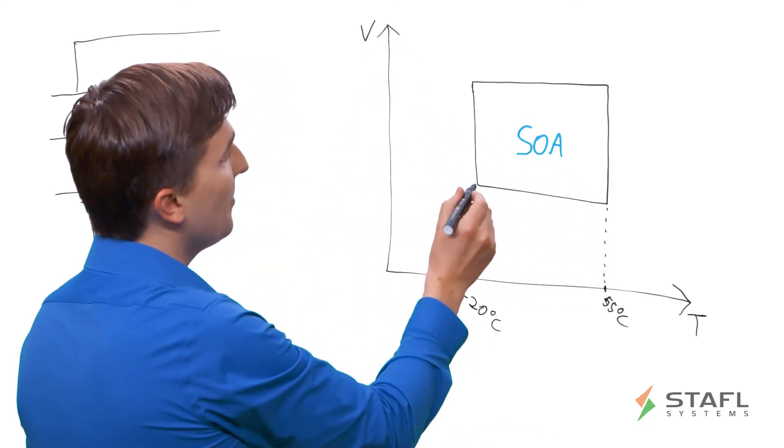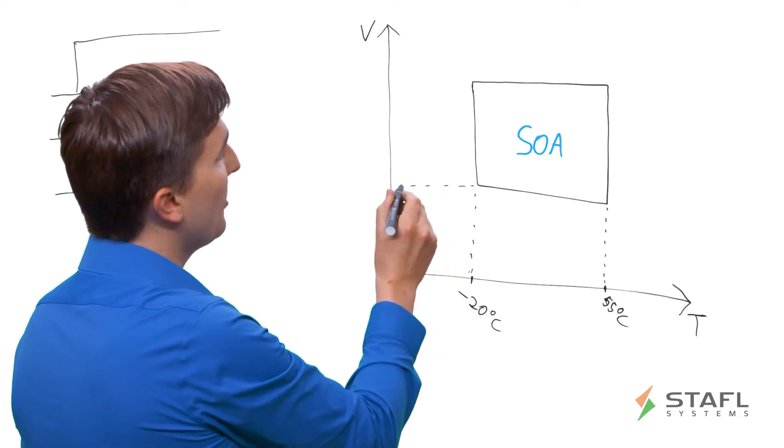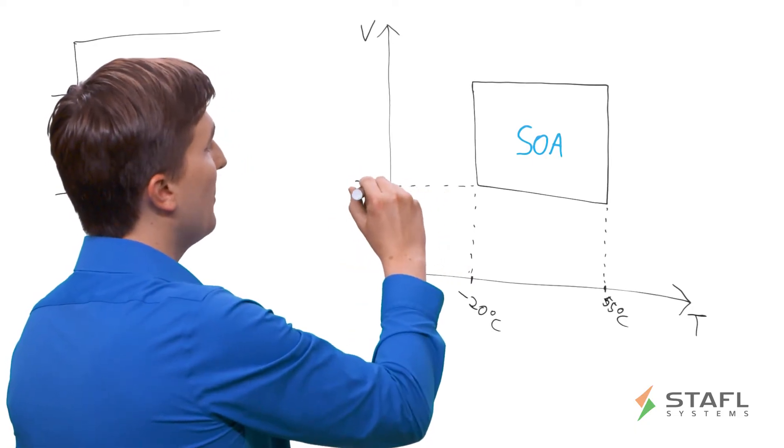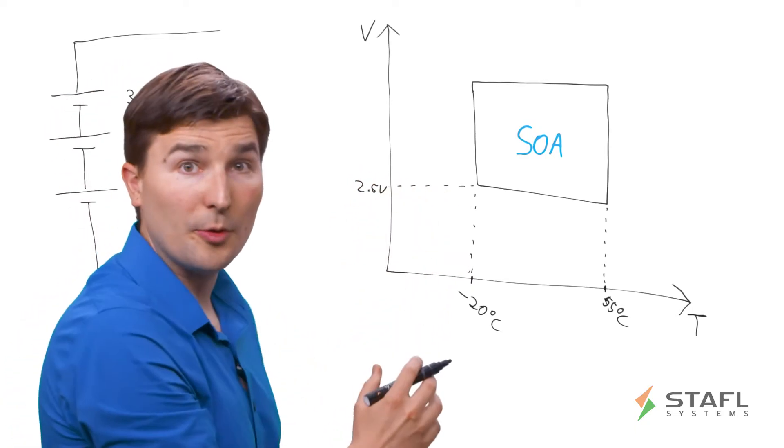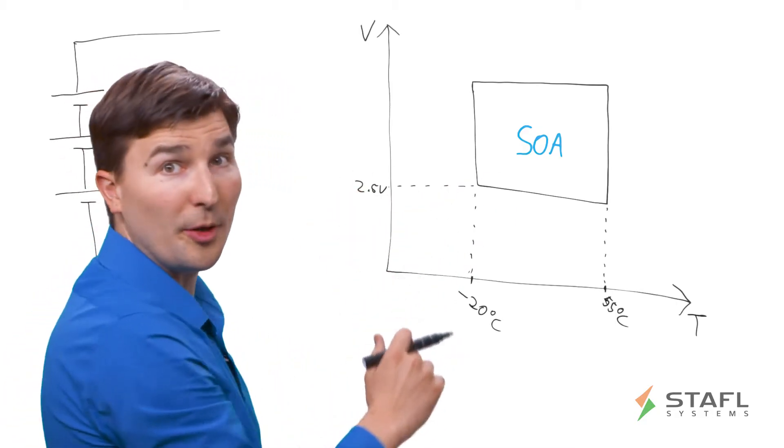On the y-axis, on the lower bound of the SOA, we have the lowest safe voltage for the battery cells. And this is 2.5 volts, typically for say, NMC chemistries.